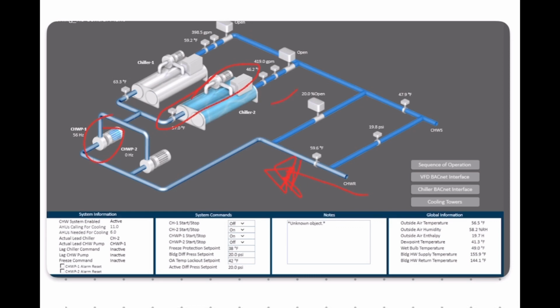Because remember, only pump 1 is running, and your chiller 2 is running, and it goes through there, and then it goes back to your building. That's your chill water supply to the building. It goes out through that line coming out of the chiller bundle or chiller evaporator, and it goes to your building.